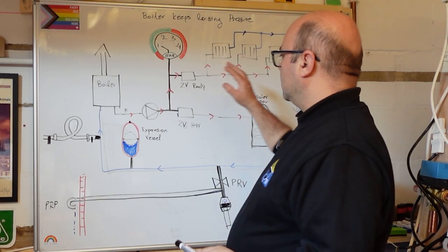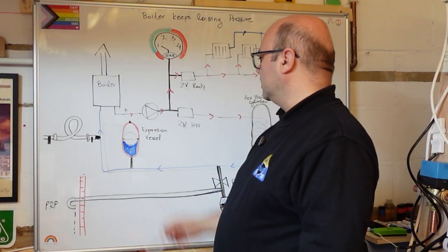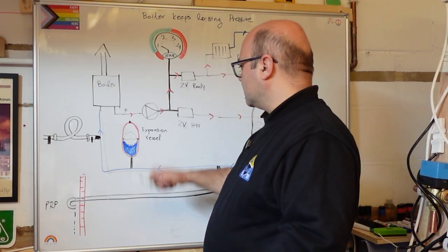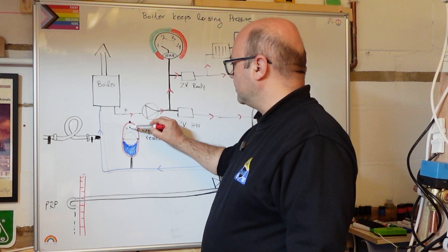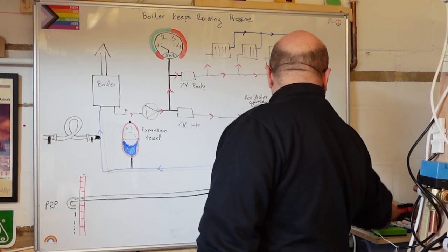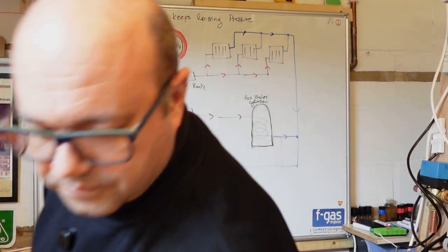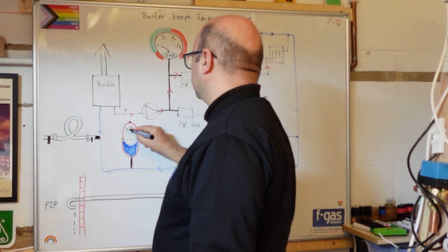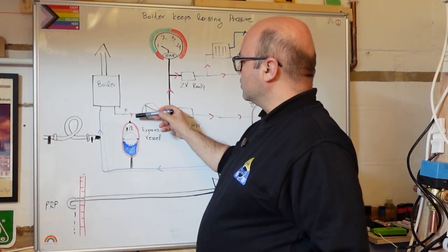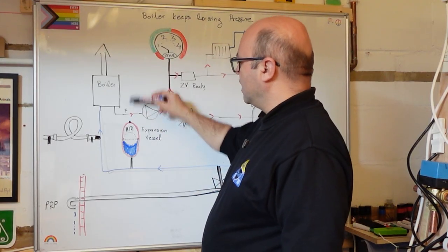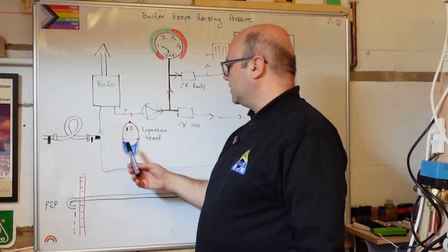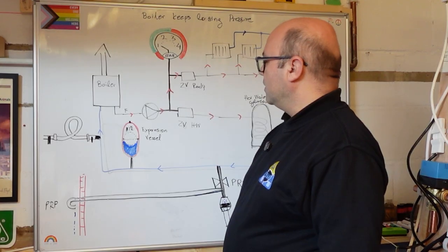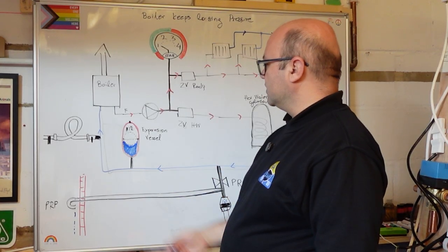First of all, as we're getting older, the expansion vessel inside the boiler loses the flexibility to bring the balance. In other words, this is the water, this is the air into the system. Sometimes, of course, the air disappears from the valve, wear and tear, or sometimes the water goes inside to the rubber and damages the expansion vessel. A lot of reasons as we're getting older can damage the expansion vessel.